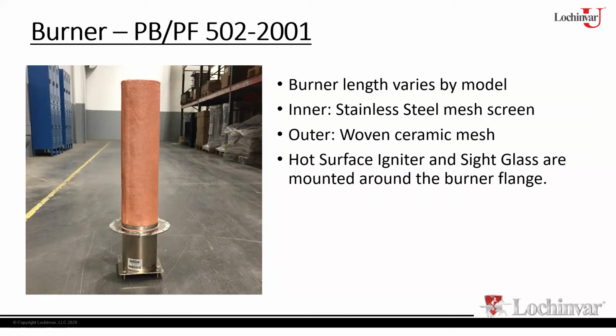But basically the burner is going to be running full tilt. Our lab supervisor, who generally does the demonstration, Jeff Cooper, will shut the burner off as it's running at its maximum and then immediately put his hand on it, and run his hand up the surface of the burner, which is very impressive because right before that, you just had this huge ball of flame sitting there, and he shuts it off and puts his hand on it and doesn't come away burnt. So again, what we're doing is keeping that air forcing through the burner, which keeps the surface of the burner relatively cool. So that flame never comes in contact with it. When you get burner damage, and this applies to any burner, it's because the flame is pulling into the surface of the burner. And when you put that hot flame on the surface, that's when you get the damage. So that's what we're trying to prevent.